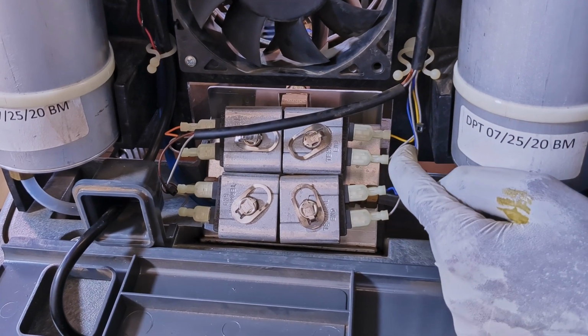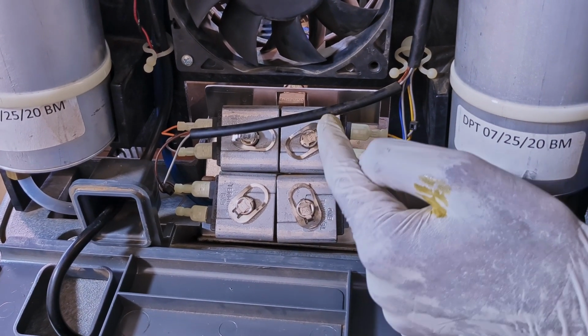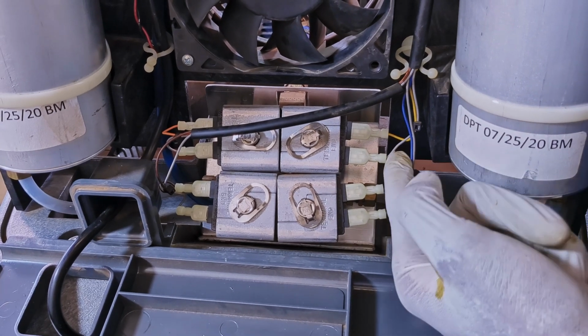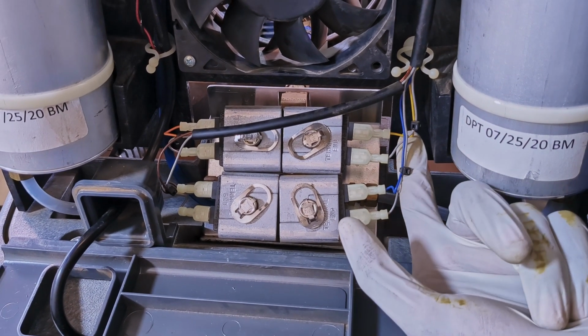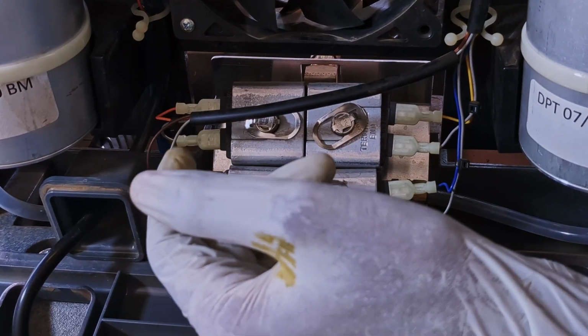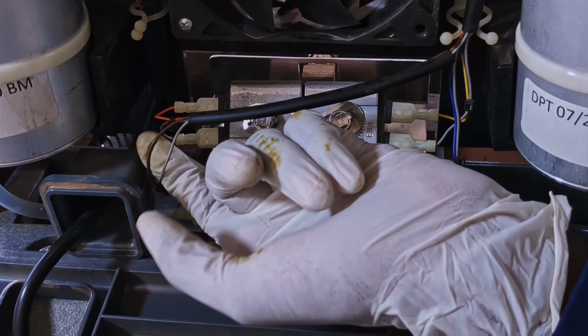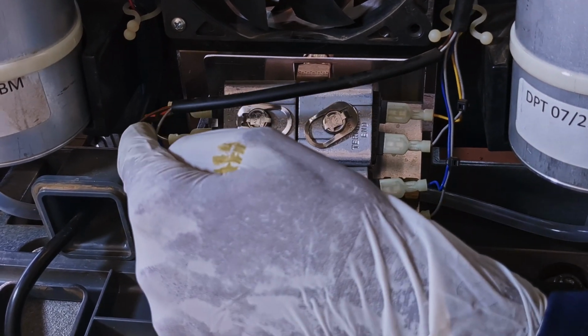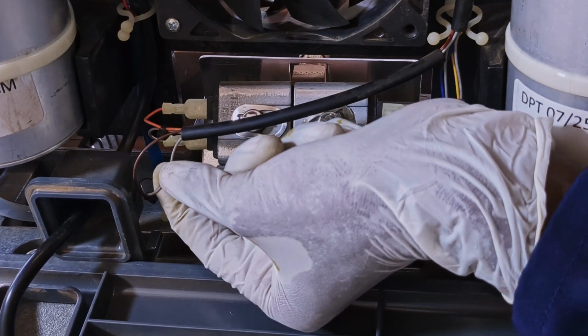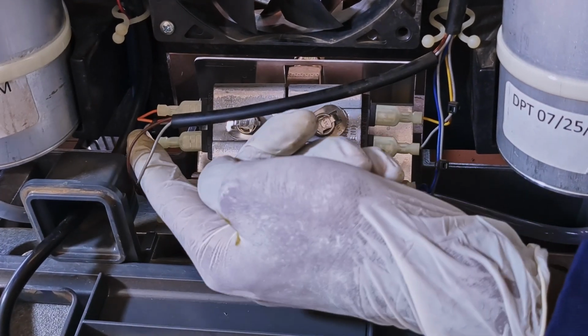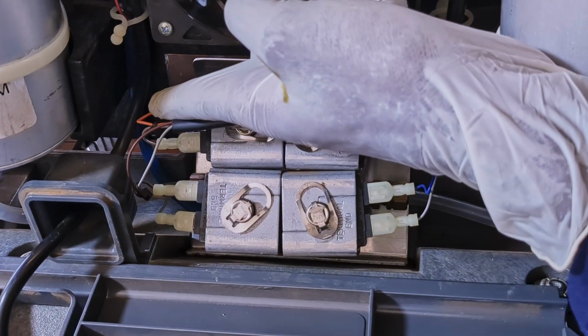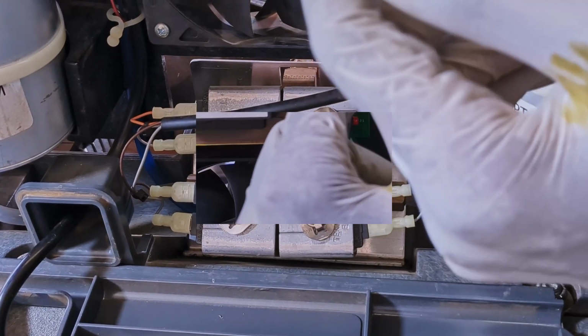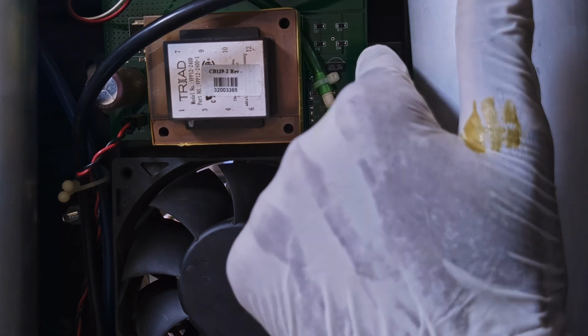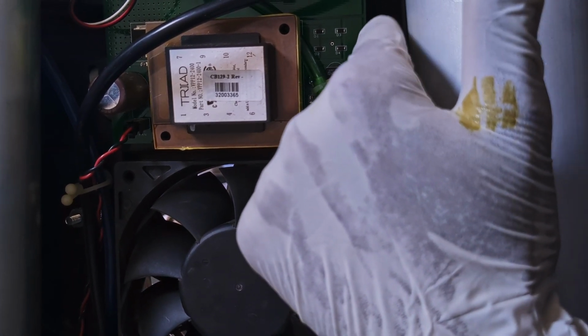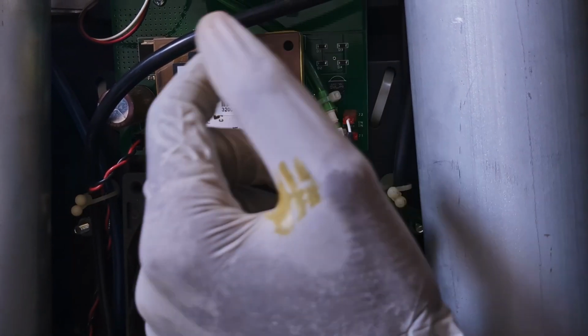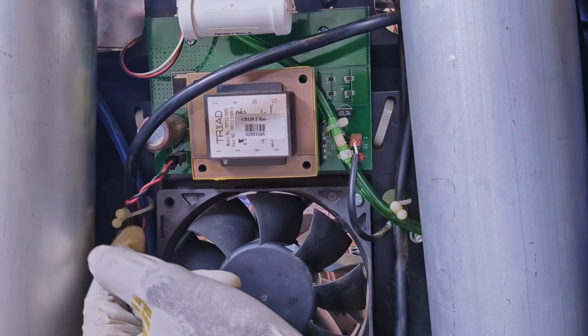And over here we have this one, which is the live cable, and the yellow one for the neutral. Similarly, on the other side we have this one, which is the neutral, and this one, which is the live. And lastly, this one, which is the live, and this one, which is neutral. Over here we have the fan control board. It receives 230 volts AC and converts it to DC. The DC output is used to power the fan.